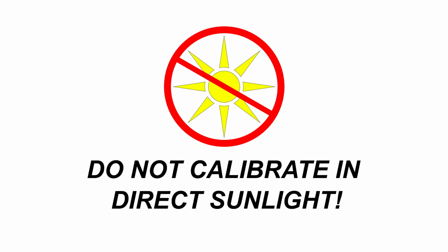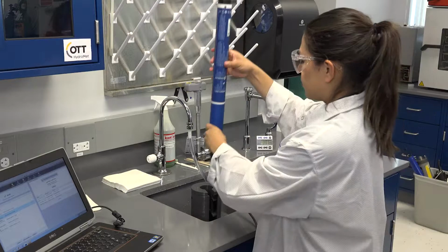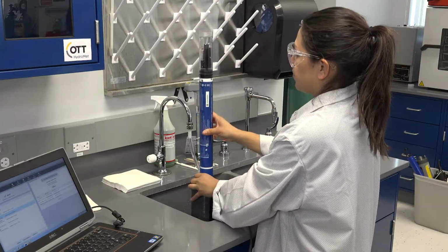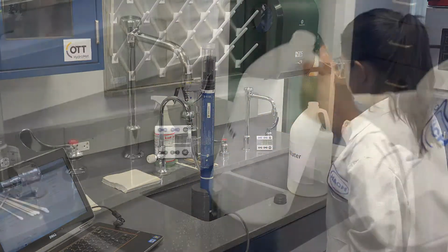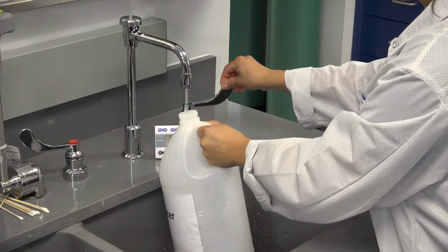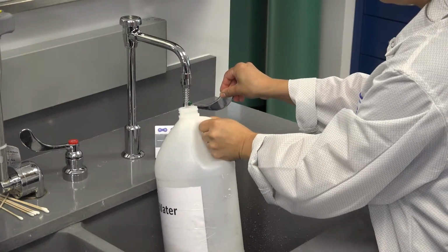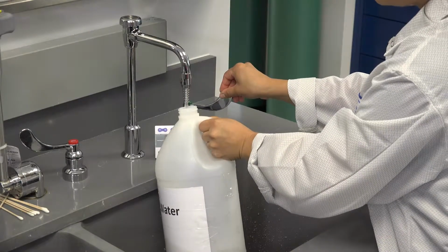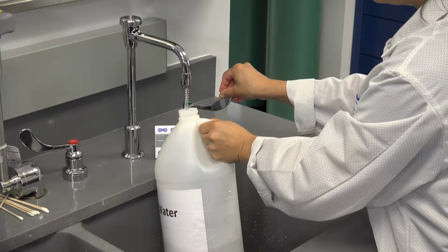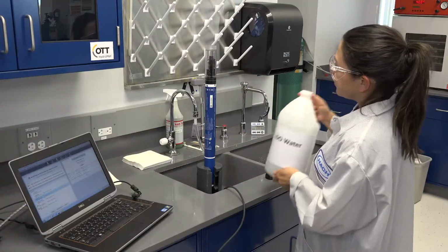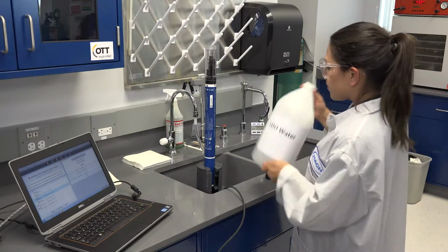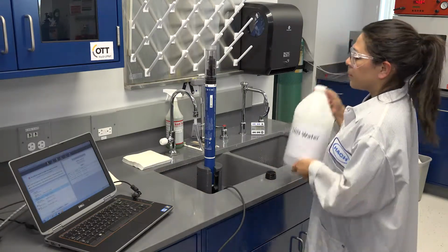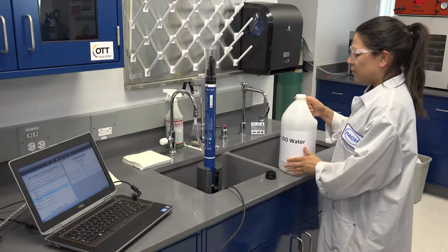For this reason, the calibration should also not be done in direct sunlight. Stand the sonde so that the sensors are pointed upwards with the storage cup attached. Add about 1 liter of room temperature water, or clean tap water with a conductivity of less than 500 microsiemens per centimeter, to a clean 1-gallon jug. Shake the jug very vigorously for 40 seconds in order to create the 100% air-saturated water standard required of the LDO calibration.